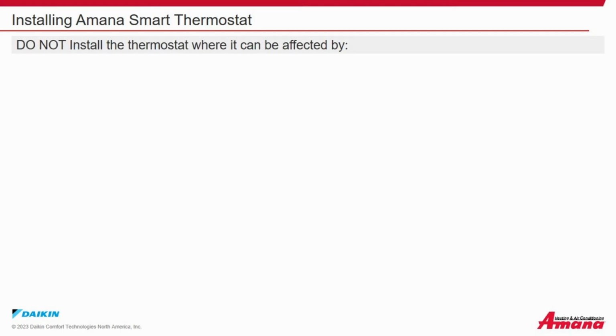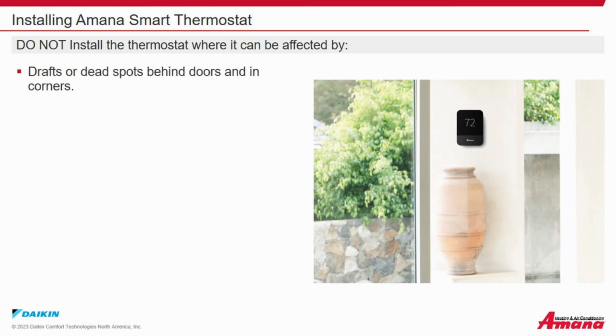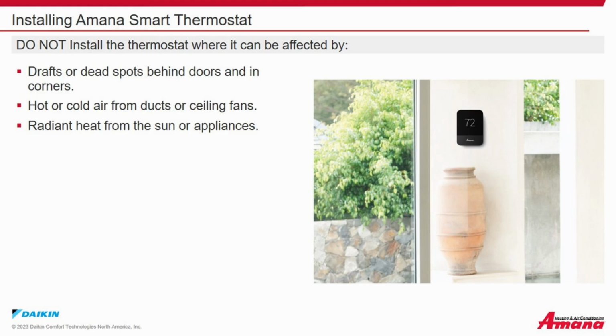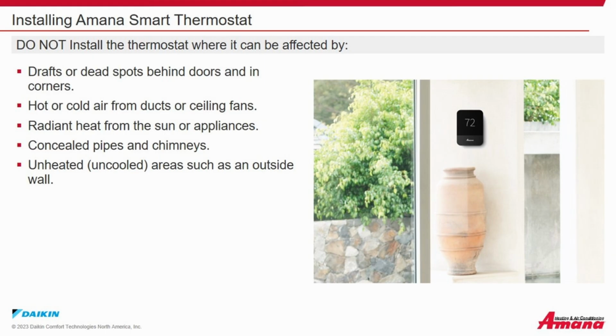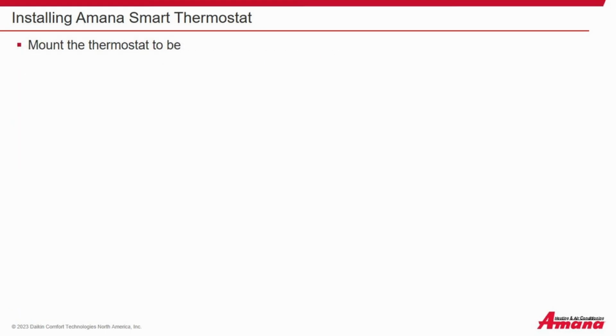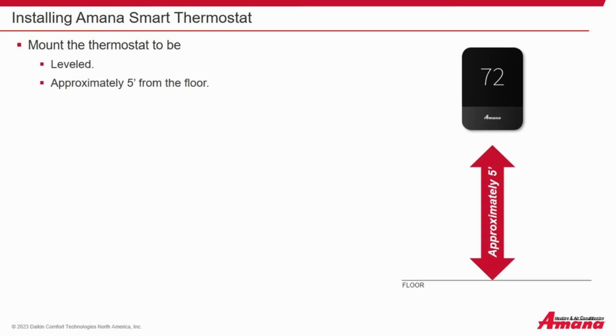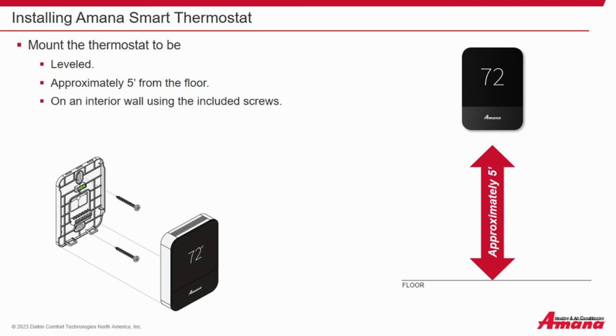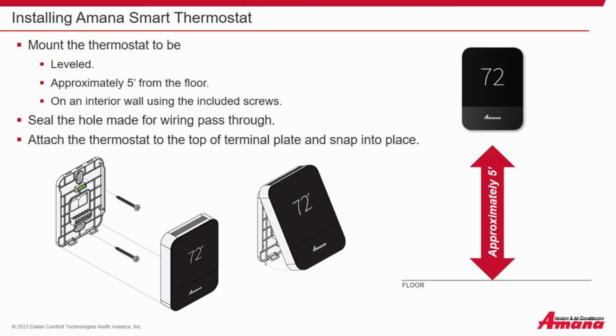Installing the Amana Smart Thermostat. Do not install the thermostat where it can be affected by drafts or dead spots behind doors or in corners, hot or cold air from ducts or ceiling fans, radiant heat from the sun or appliances, concealed pipes and chimneys, or unheated and uncooled areas such as an outside wall. Mount the thermostat level, approximately 5 feet from the floor, on an interior wall using the included screws. Seal the hole made for wiring pass-through. Attach the thermostat to the top of the terminal plate and snap it into place.